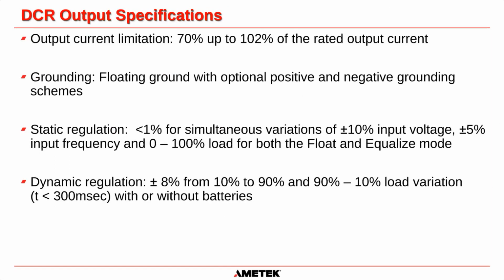The output specifications for our DCR are that we have an output current limit between 70% of the rated current and 102%. For grounding, we have a floating ground with optional positive and negative grounding schemes. Static regulation is less than 1% for simultaneous variations of plus or minus 10% on the input, and plus or minus 5% of the input frequency, and 0 to 100% load for both float and equalized mode. And dynamic regulation is plus or minus 8% from 10% to 90%, and 90% to 10% load variation in less than 300 milliseconds, and that's with or without batteries.